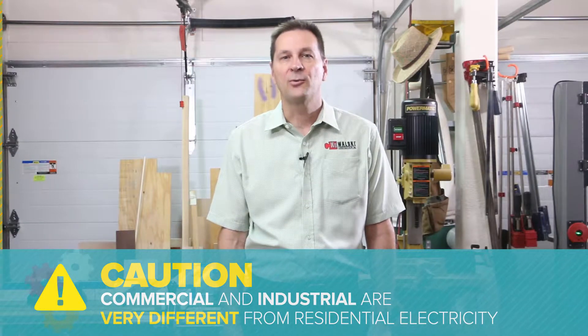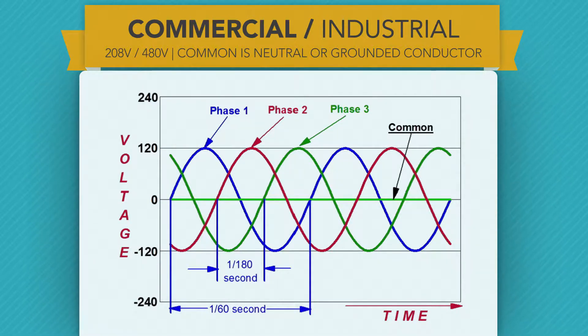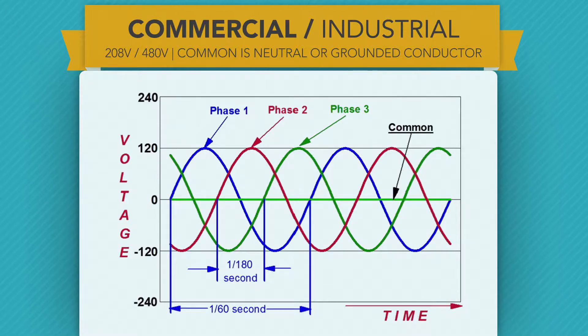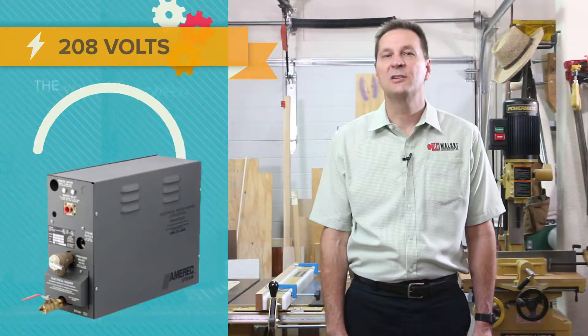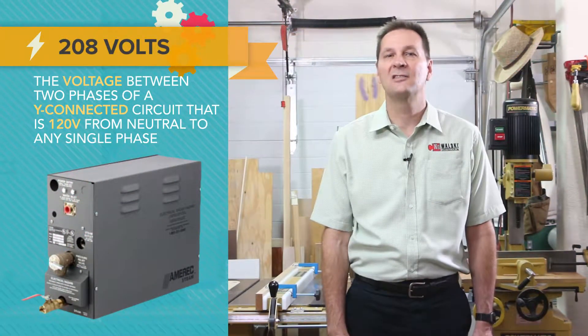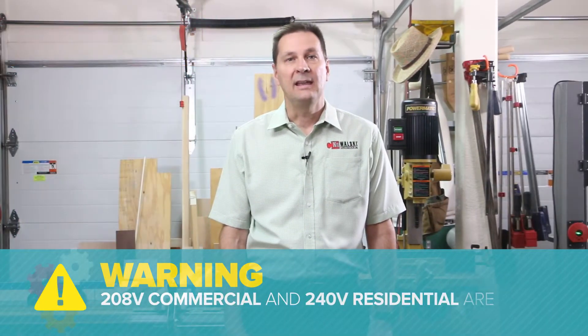On three-phase four-wire Y-connected systems, you can see that an entire cycle of the voltage wave — starting at zero, going all the way positive, then back through zero, then all the way negative, and back to zero again — is still taking one-sixtieth of a second for each of the three phases. 208 volts is the voltage between two phases of a Y-connected circuit, that is 120 volts from neutral to any single phase.